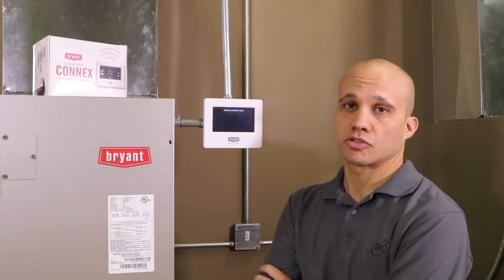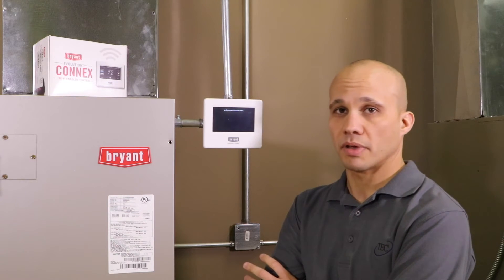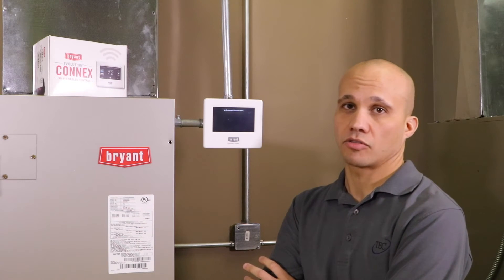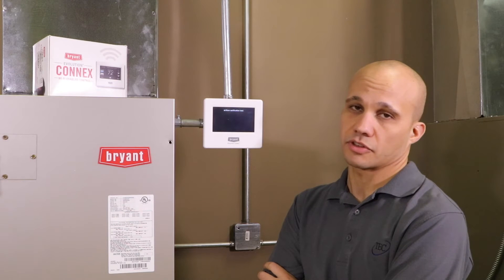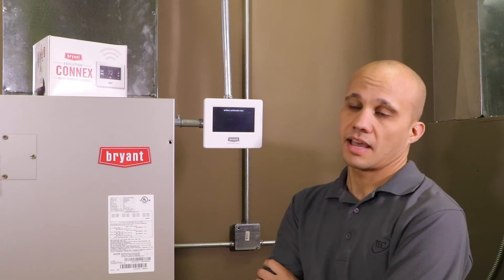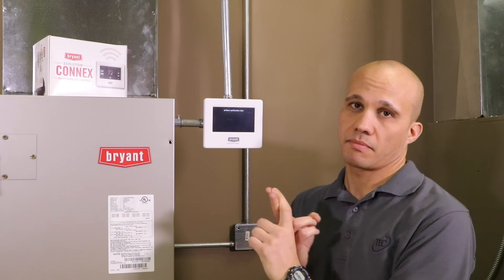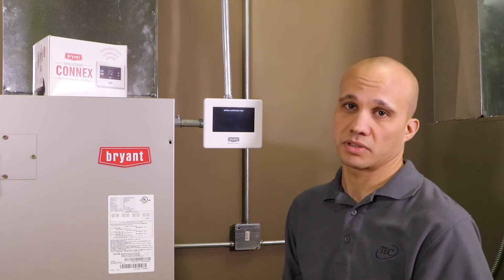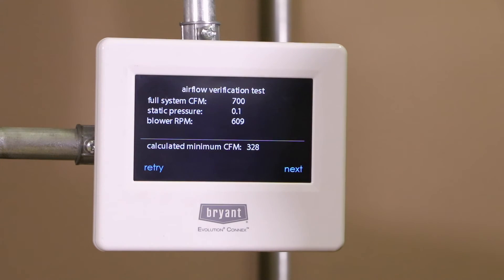This is our airflow verification test. It's going to run the furnace or fan coil at various capacities to test its airflow. As you may know, this is variable speed equipment, as all Evolution and Infinity equipment is. It's going to run at different speeds and has the ability to track the RPM, CFM, and static pressure of this motor, then give us a report back with that data.